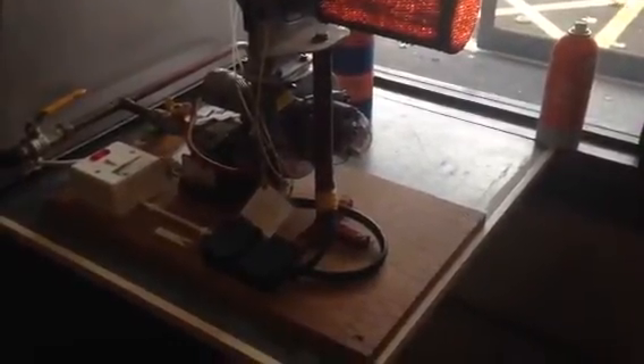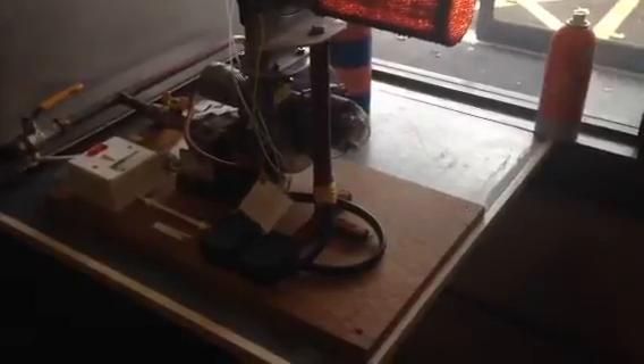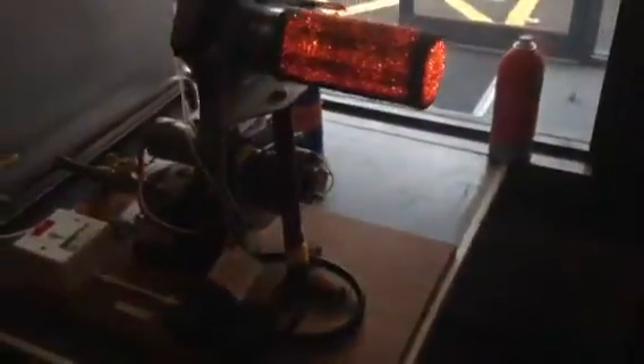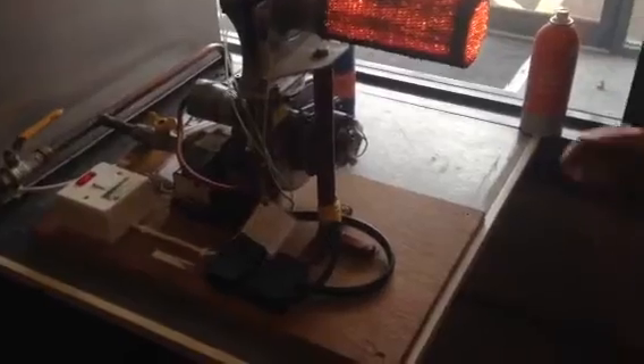Yeah, that's what it does. So it's instant. As soon as there's no flame, it will shut the valve off, shut the solenoid, cut power to the solenoid, shut it down. Then it'll go through a purge cycle again, and it will try to reignite. So now it's purging the gas and air from the exchanger.